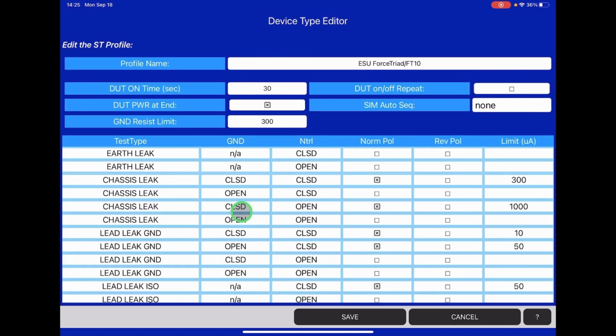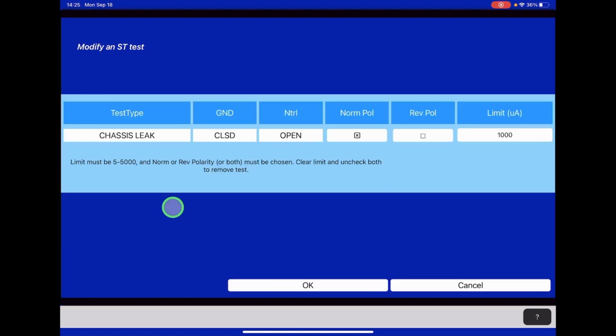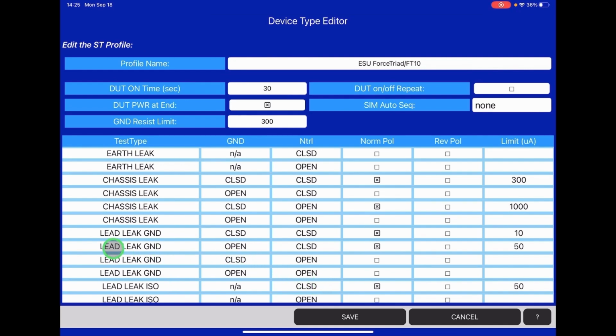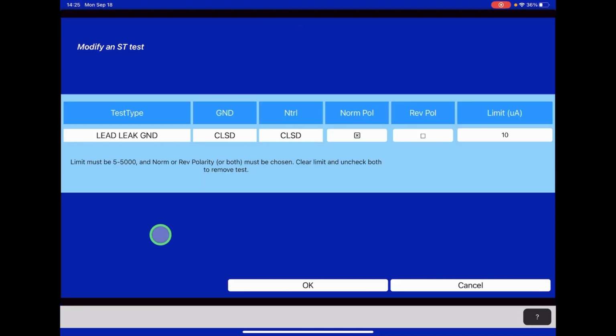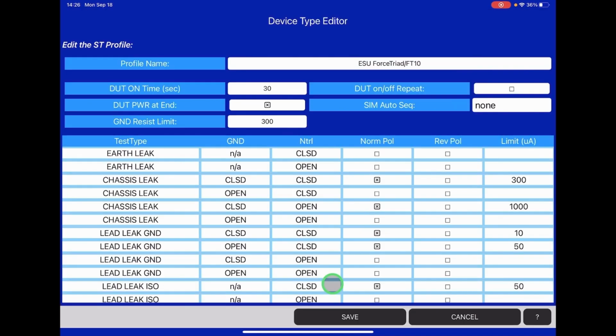That's one test. The next test is we have to also do a chassis leakage test with the neutral open. That's why you see this configured open here. We're going to do it again in normal polarity. Reverse polarity remains off, and the limit in this test is 1000 microamps. The next test down is the lead leakage to grounds test. We need to do this in normal conditions, and so that's why you have ground and neutral closed. Normal polarity only again, and the limit is 10 microamps.